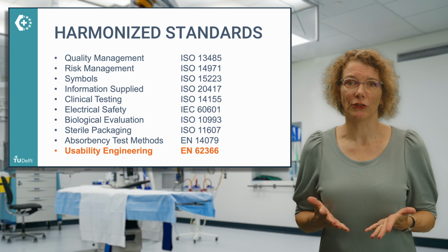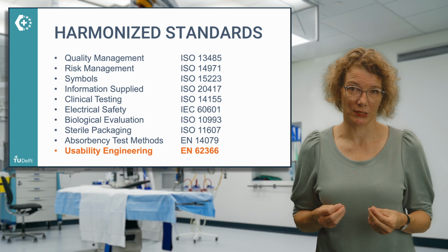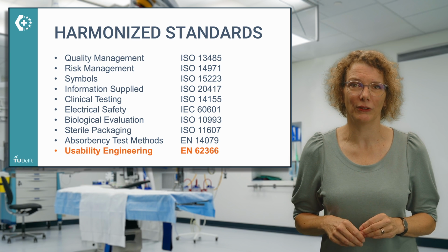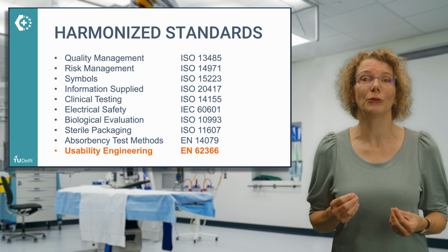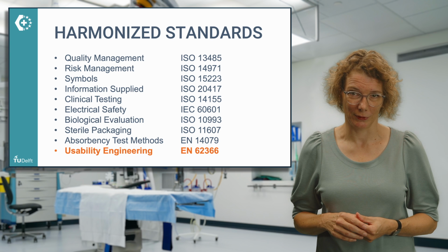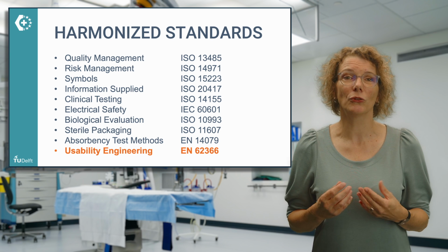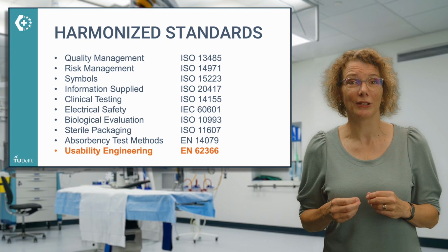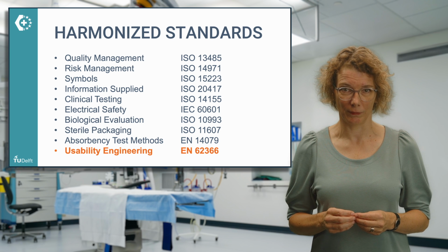So far, I mainly mentioned example harmonized standards with requirements on physical properties of medical devices. Being a design engineer myself, specialized in human factors and usability evaluation, I also need to tell you more about the MDR's expectations on usability validation, of course. At the time of this recording, being August 2024, the most recent usability engineering standard, IEC 62366-1 from 2015, is not listed as a harmonized standard.